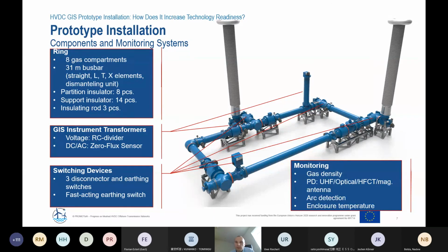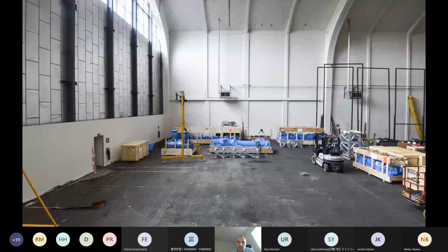And the pole is also equipped with monitoring systems, which are typical monitoring systems that would be used in a real installation, and also with a few more experimental systems. So we had the gas density monitoring, we had to monitor PD activity, we had the UHF system, but also an optical system, HFCT system, and a magnetic antenna. I think especially about the more experimental systems, we will hear more in the third session by the PROMOTioN partners that worked on that. We had arc detection and enclosure temperature measurement throughout the test.